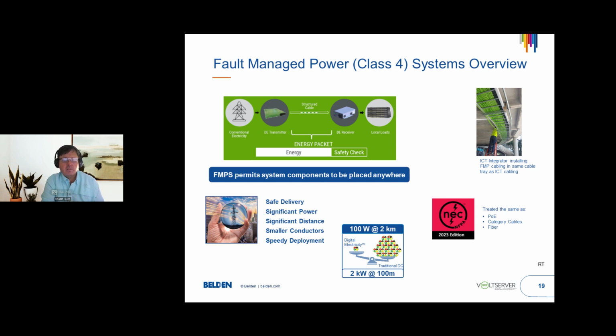Now, if I go back to the argument of class 2, I can still do these same things with class 2 cabling - I'm talking here a DC line voltage type of class 2 power supply, not PoE, it wouldn't make sense there. But if you look at a typical class 2 using a DC power supply, with that same 4 conductor cable, I would need 18 of them to do 100 watts at 2 kilometers, or I would need 18 of them to do 2 kilowatts at 100 meters. Now, mind you, it'd be a lot of soldering that would have to take place for that to happen, but you get the idea.